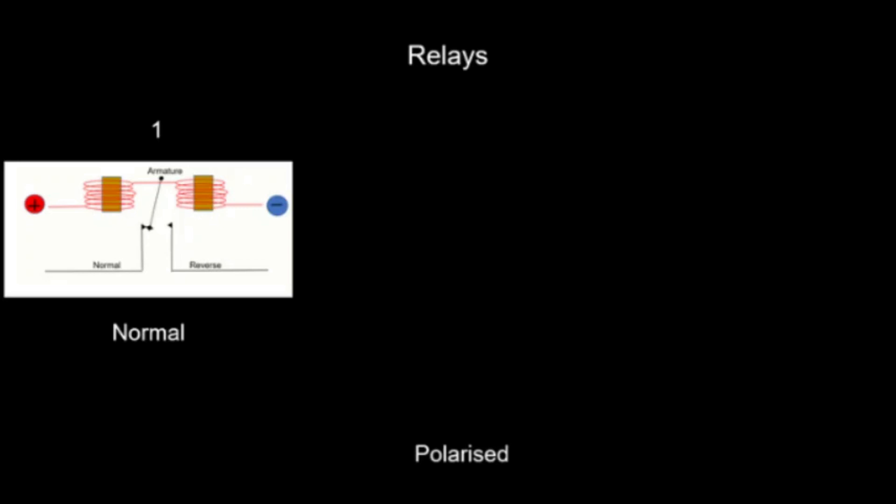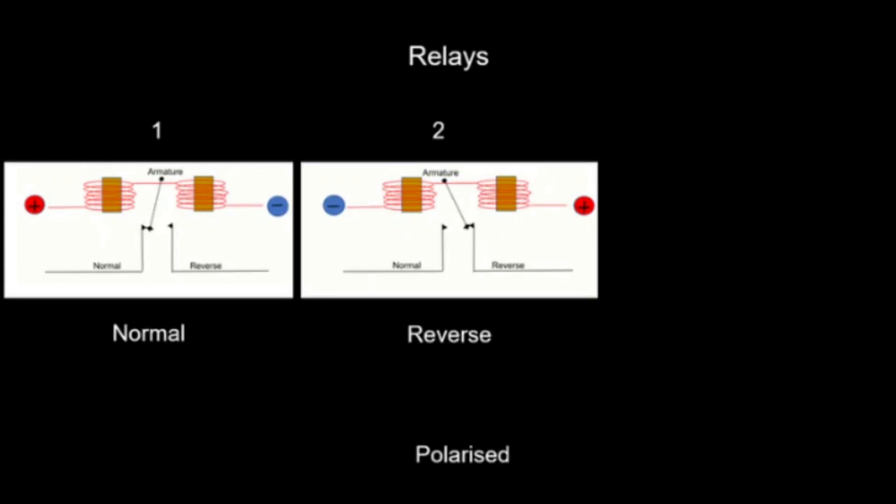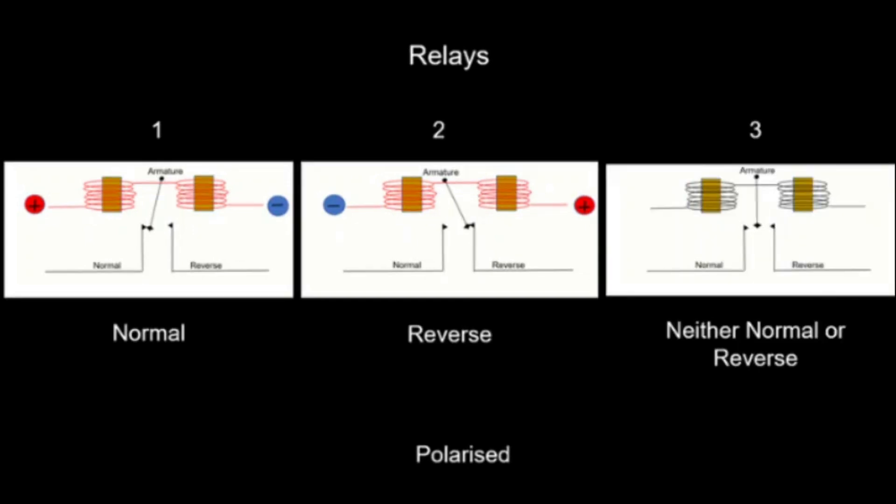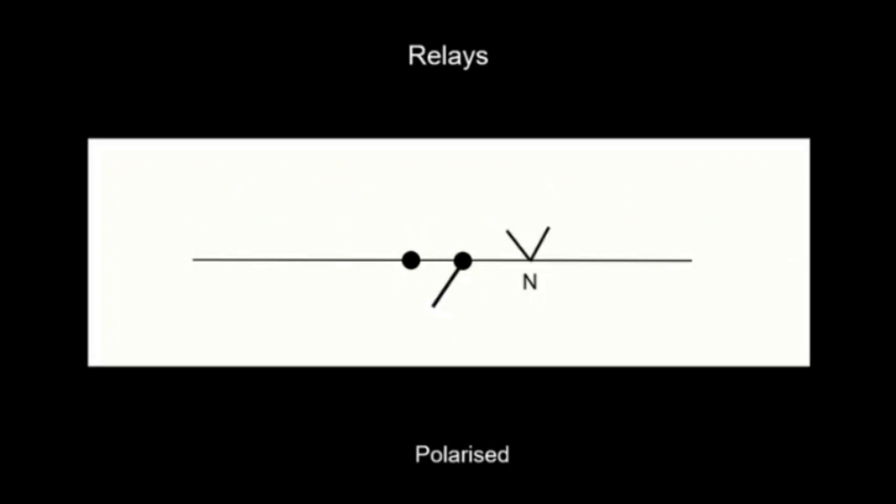If polarised in one direction, the armature connects with the contact known as normal. If the polarity is reversed, it connects with the reverse contact. Or it is not connecting with either normal or reverse when there is no current flow. This is how a polarised relay contact is shown in signaling diagrams.